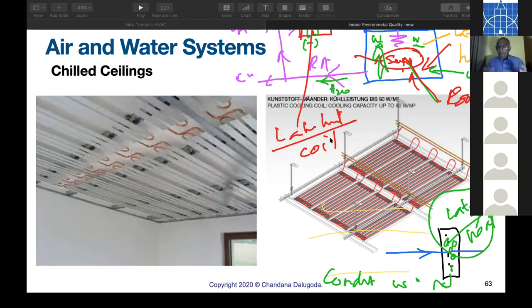Now, passive sensible coil means the cooling coil will operate above the dew point. So there will not be any condensation. So how do we now tackle latent load here? You know what we do? We'll have to couple a special air conditioning system that we are going to discuss later.